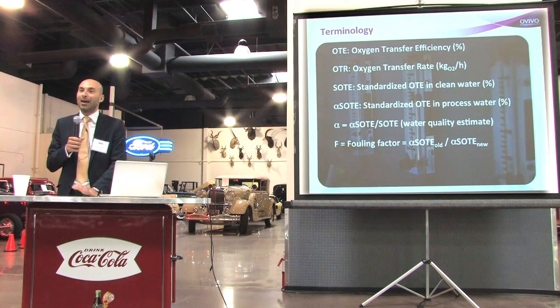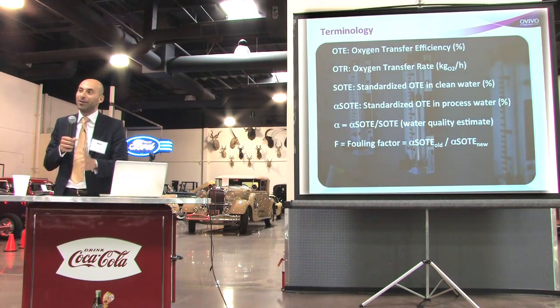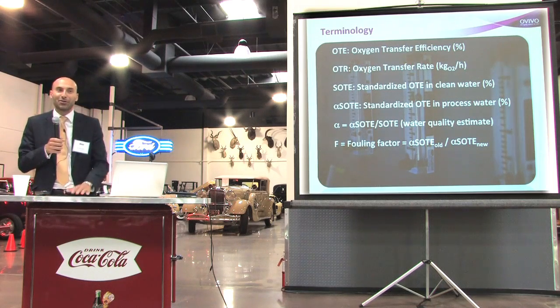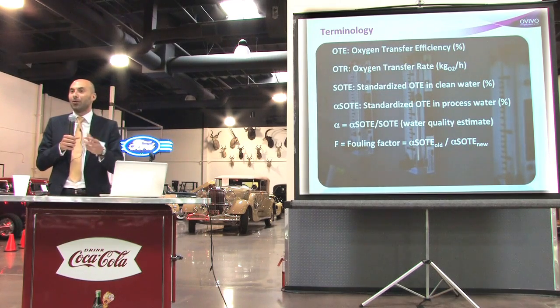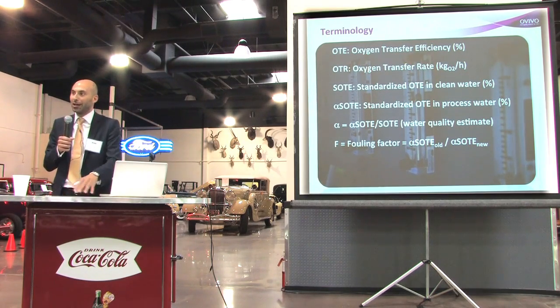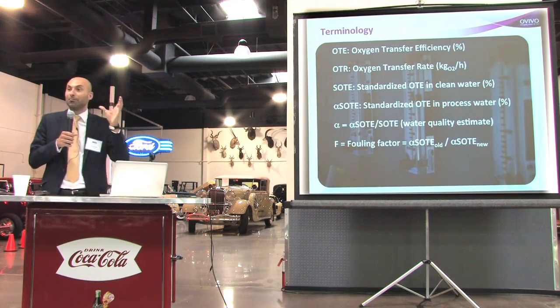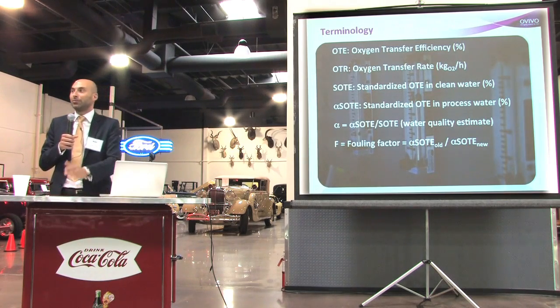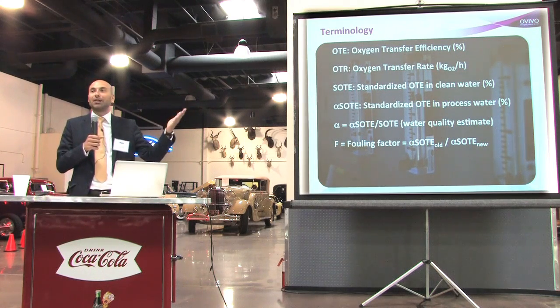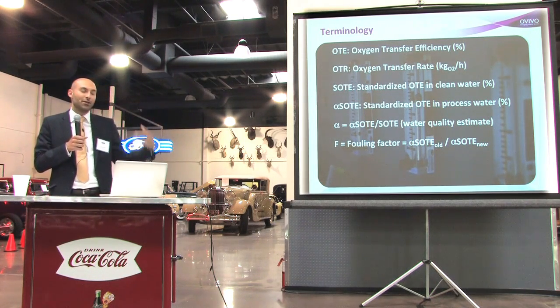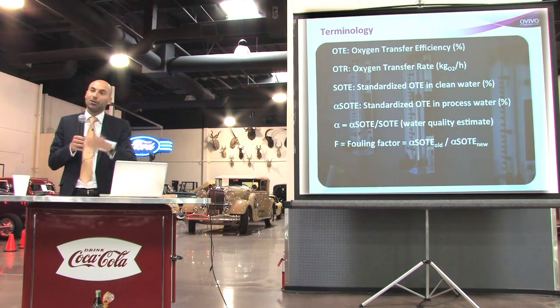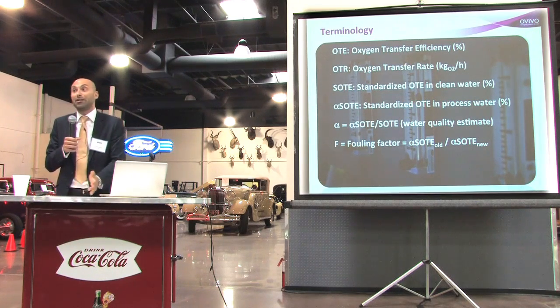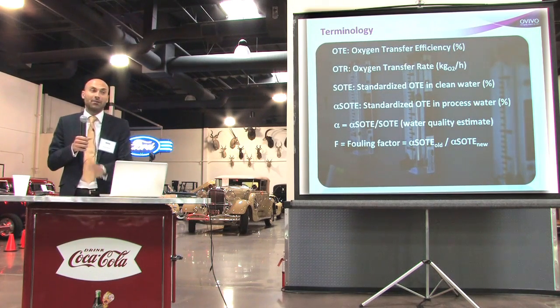Over time, diffuser efficiency inevitably goes down — just like a car runs well when new and loses efficiency over time. We measure alpha over time, or the alpha·SOTE product (your design value), starting from day one and then every three to six months or every year, watching a curve of alpha declining over time.